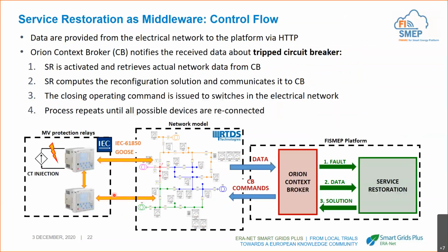This is the final test setup that we have used. So we have simulated the grid with our real-time digital simulator, which is able to interface with communication cards with our Fismep platform. On the other side, it is also able to communicate with the medium voltage protection relays, which are the industrial devices that we have in the field. In our test laboratory, we inject the overcurrent into the relays, which then trips because they detect the fault. They communicate with the standard communication protocol that a fault occurred, so they open the respective switches in the grid.